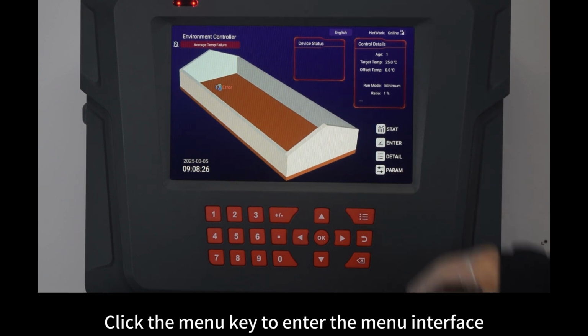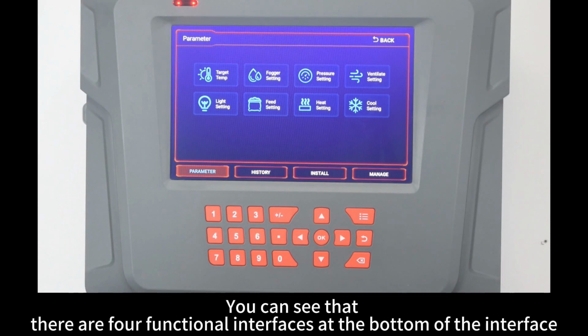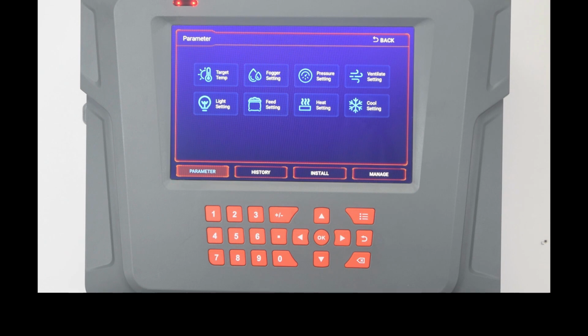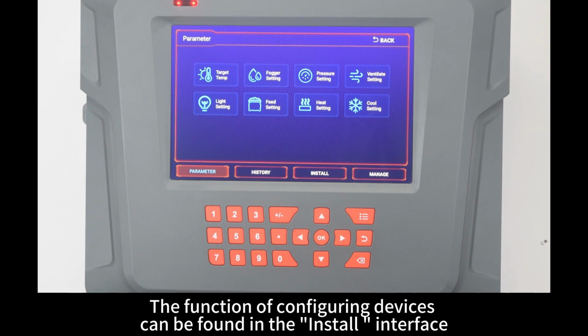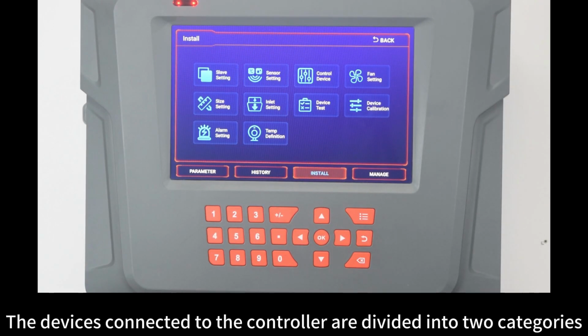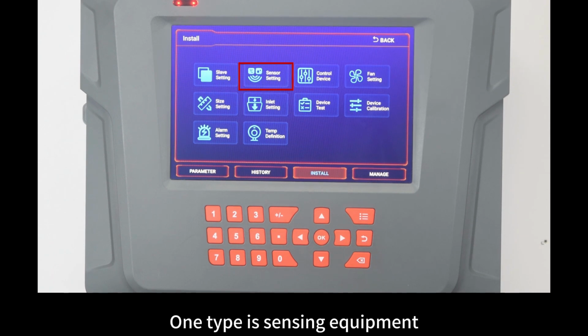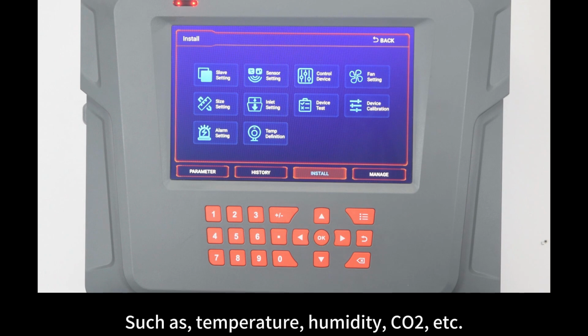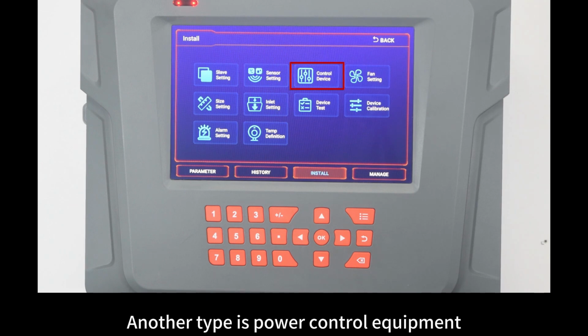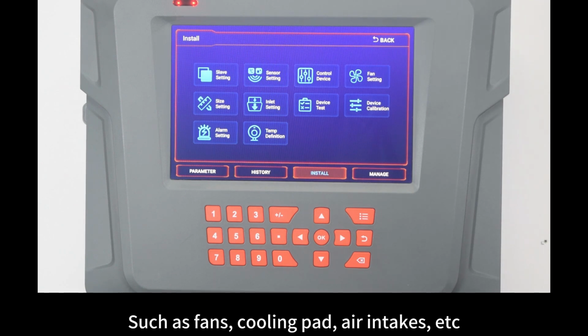Click the menu key to enter the menu interface. You can see that there are 4 functional interfaces at the bottom of the interface. Parameter, history, install, manage. The function of configuring devices can be found in the install interface. The devices connected to the controller are divided into 2 categories. One type is sensing equipment, such as temperature, humidity, CO2, etc. Another type is power control equipment, such as fans, cooling pad, air intakes, etc.